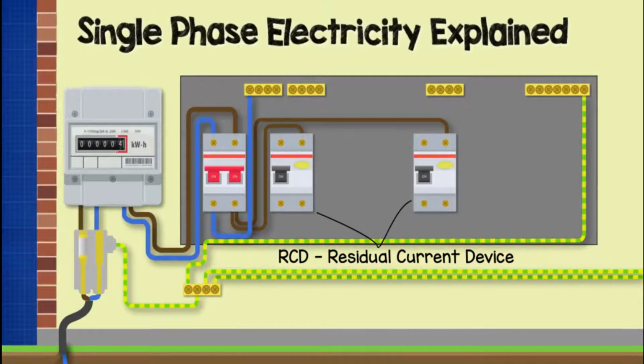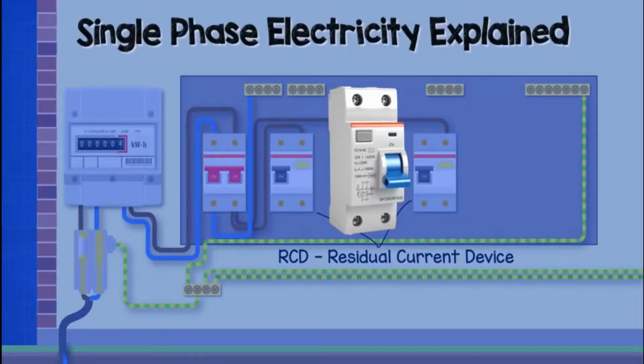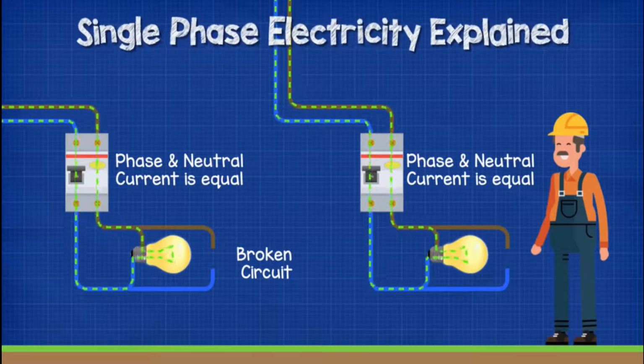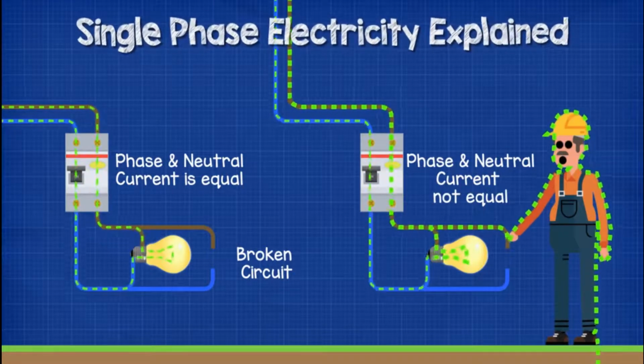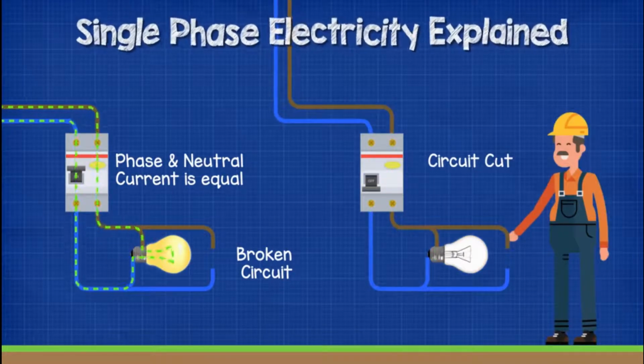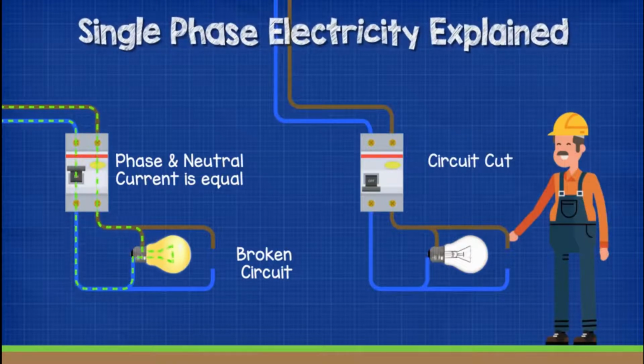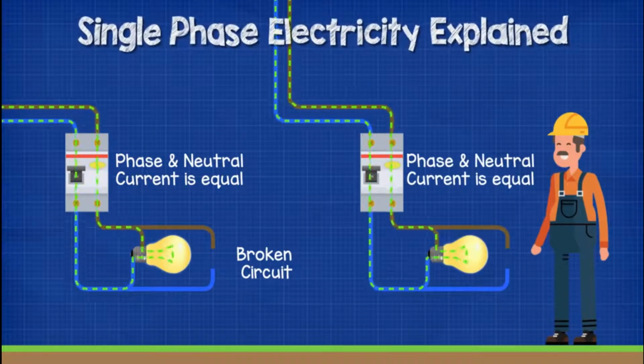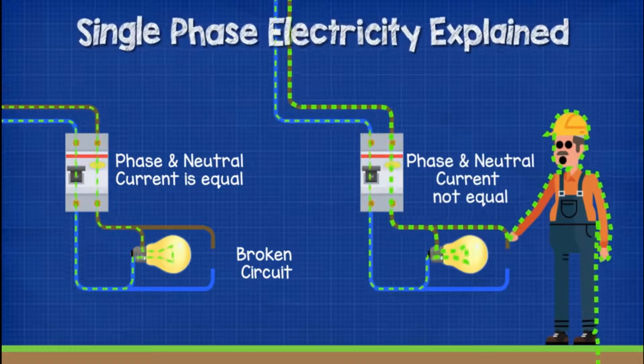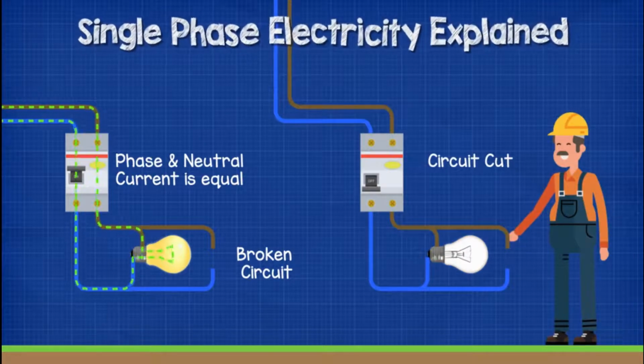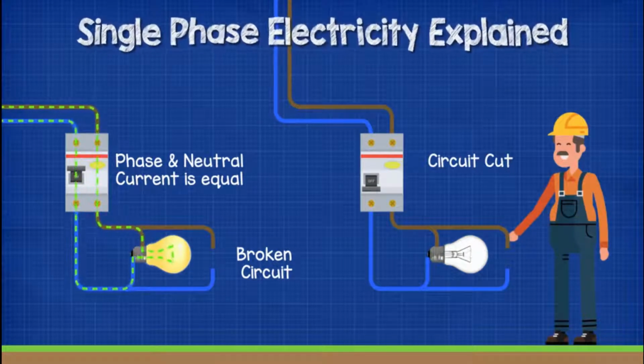This RCD switch is constantly monitoring the electrical current. It's checking if the current in the phase line is equal to the current in the neutral line. If you touch a live wire and electricity flows through you to the ground, then the current is bypassing the neutral wire, so the phase and the neutral currents will not be equal. The RCD will notice this and then cut the circuit to reduce the risk of electric shock or death.